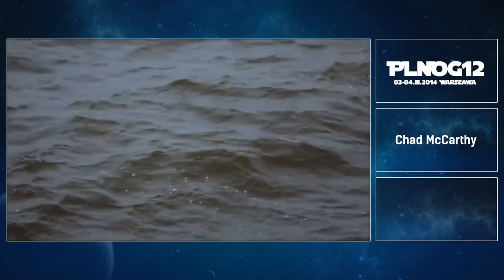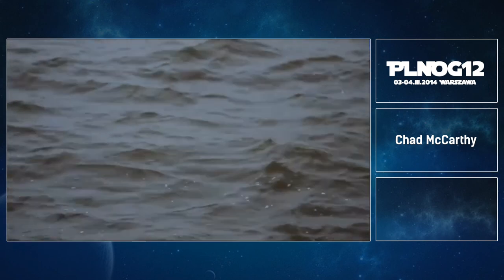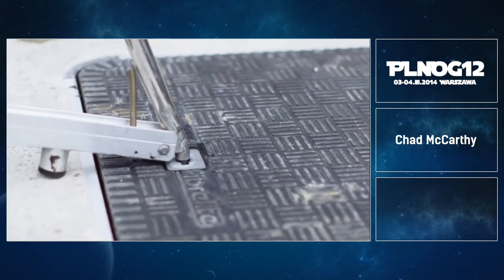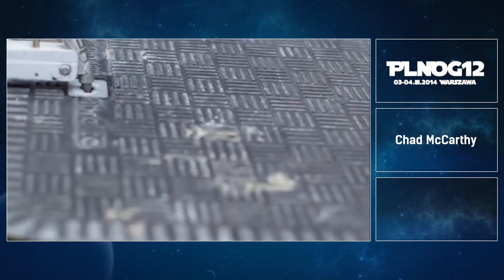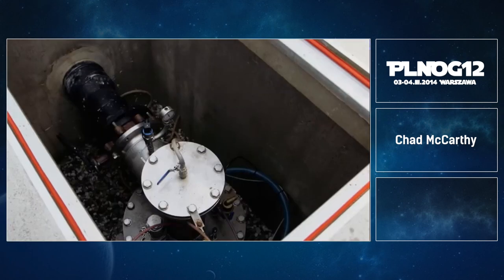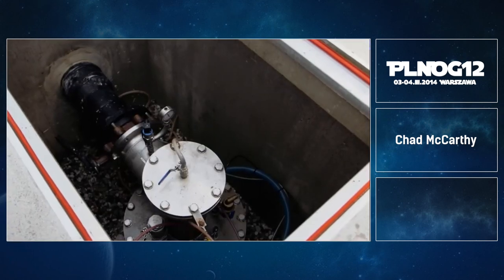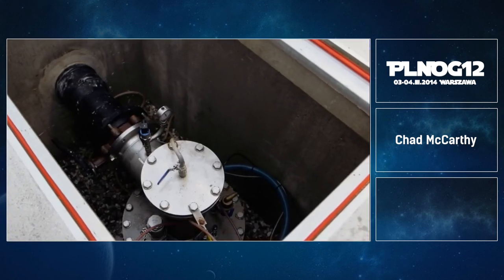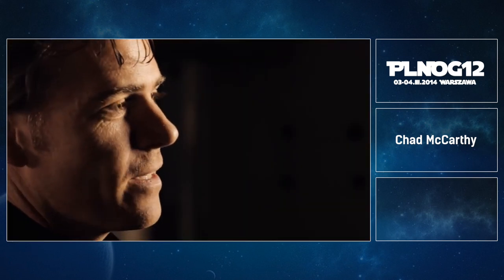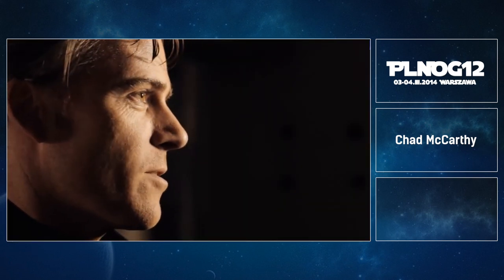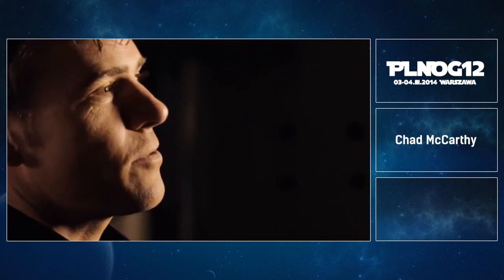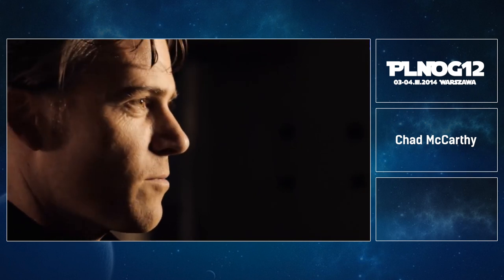But the wonderful thing about ocean water is it has a very constant temperature right throughout the year. Whereas if you're using the atmosphere, then you have a very high summer temperature, a very low winter temperature. So this is a very attractive model for data centers. We have a constant load, and here we have a constant temperature to offset that. Amsterdam is another very good example. We have a groundwater storage system where during the colder months we can cool down the groundwater, and during the hotter months we take that stored energy, which is cool, and we use it to exchange the heat from the data center back into the groundwater again.